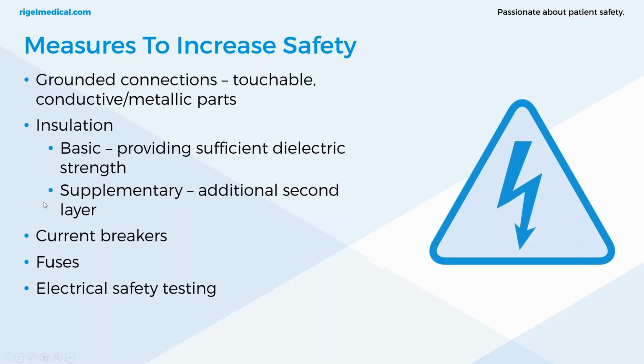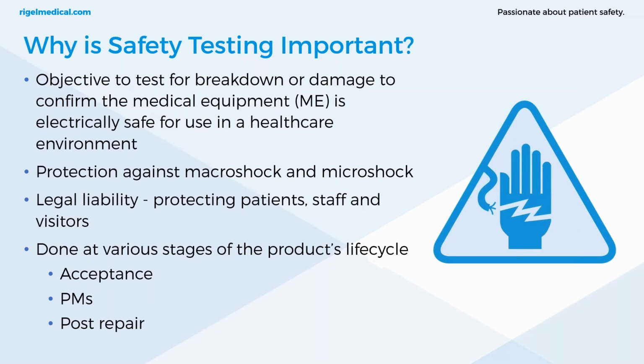And then at the bottom here, we've got electrical safety testing, which ensures that all these parameters are still performing correctly. Do we have a breakdown in insulation? Are the ground connections still safe to use? Have there been any breakdowns in the connections? So we're just ensuring with electrical safety that all these things are still performing as they should be. The objective is to test for breakdown. It gives protection against both the macro shock and micro shock factors. Legal liabilities, you're protecting patients, staff and visitors at all times.